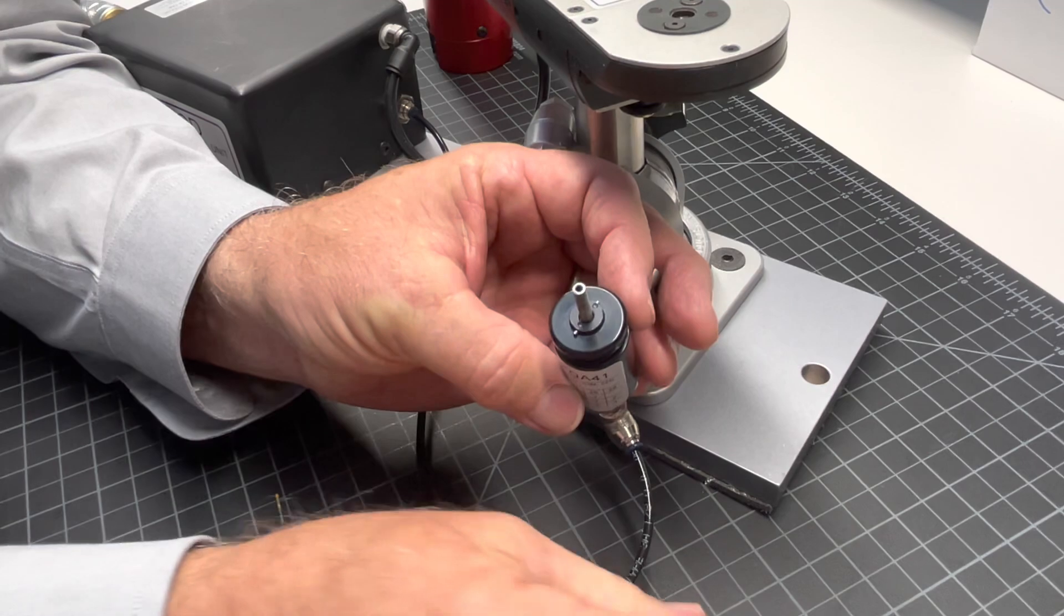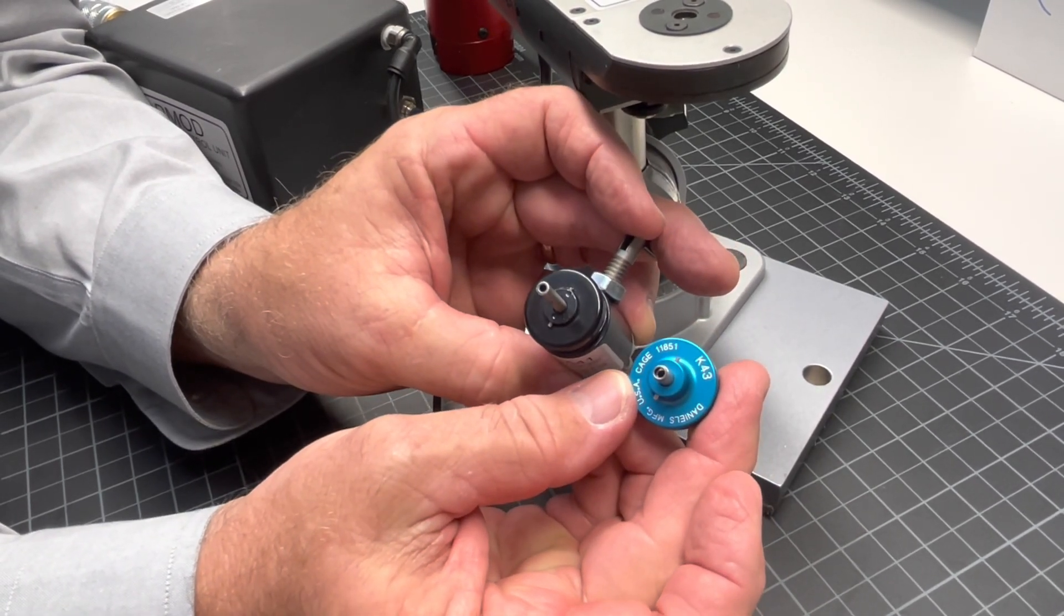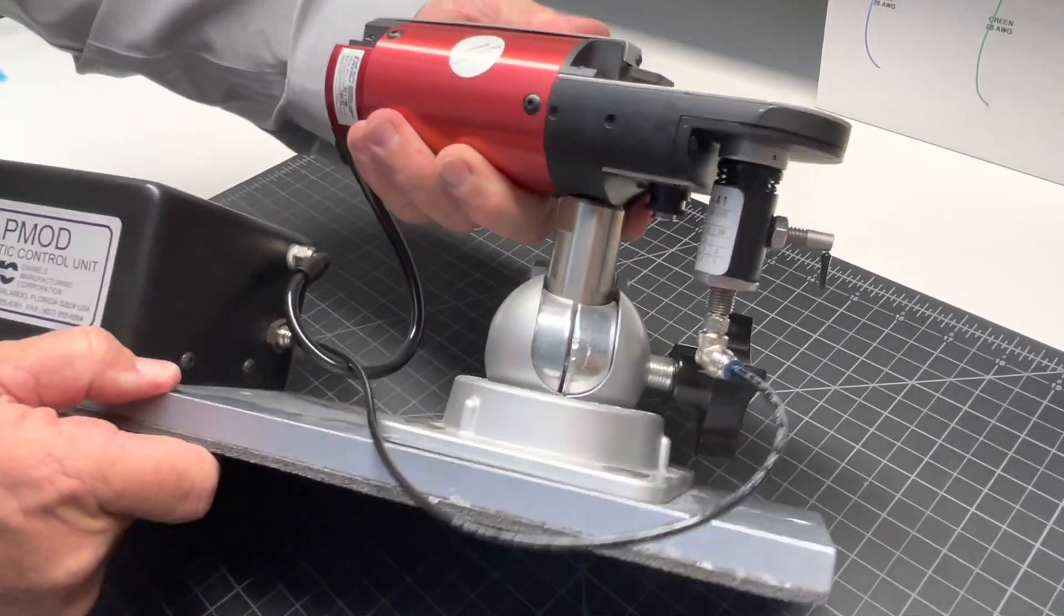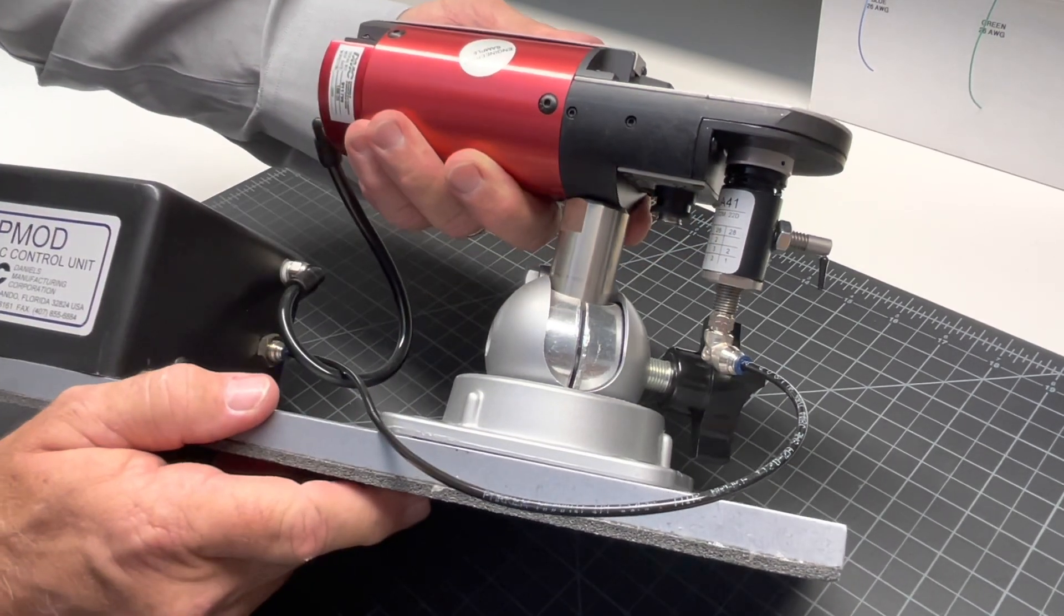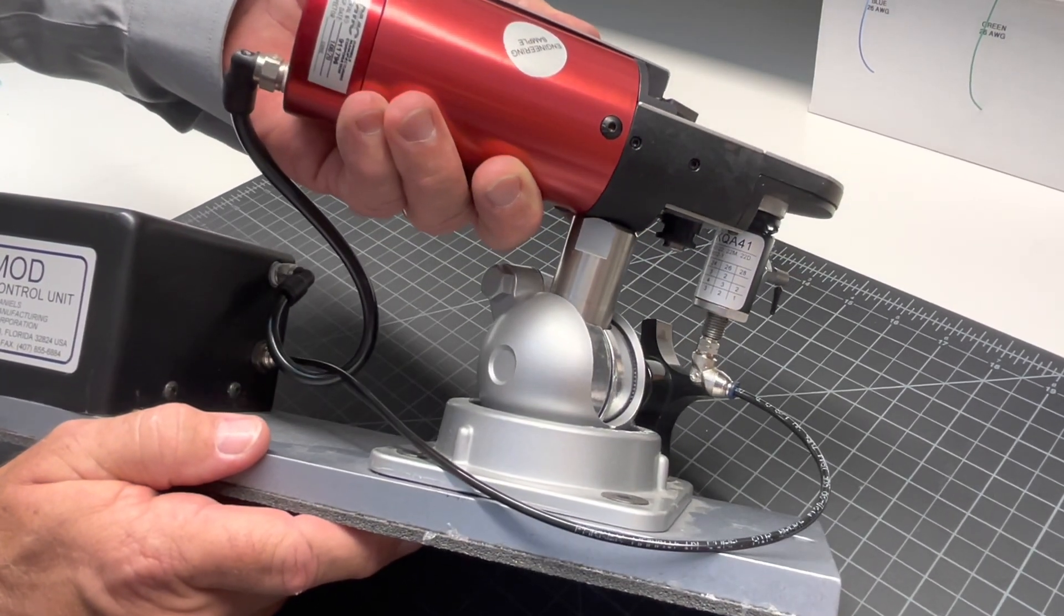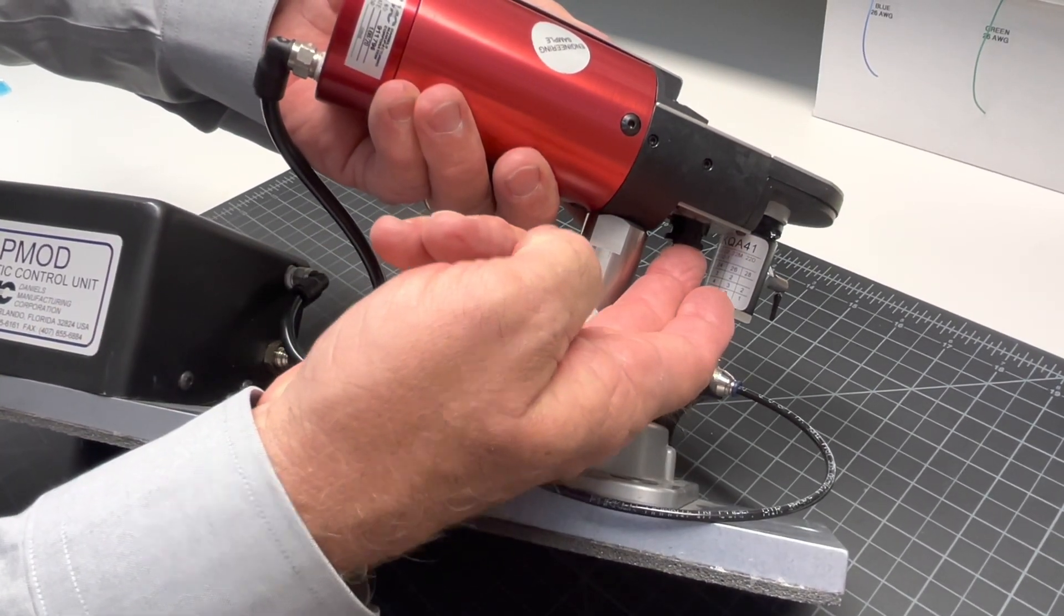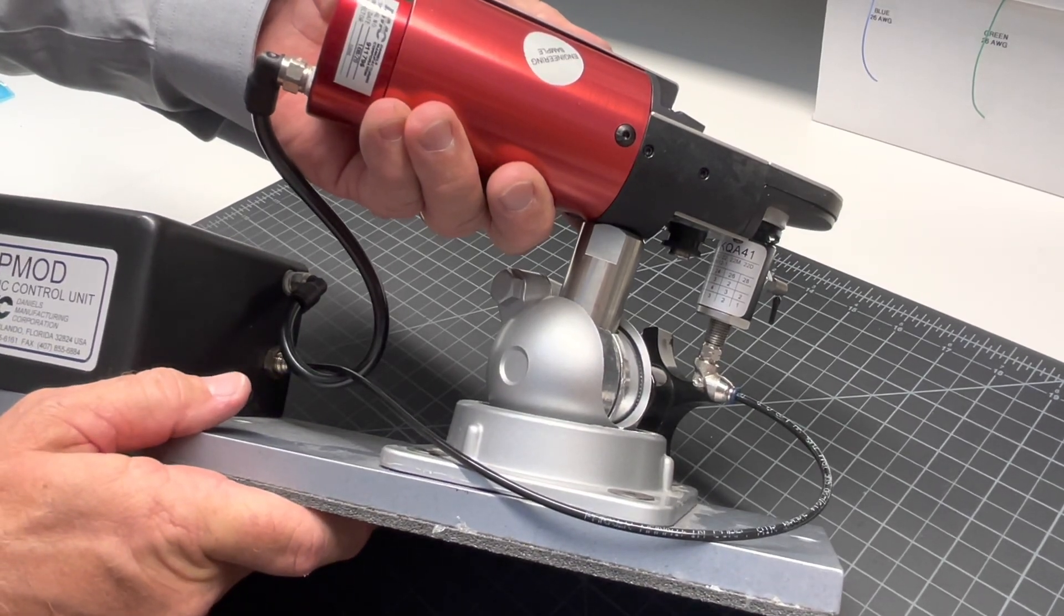They both have bayonet pins and so therefore they install onto the tool the same way. When using the APMOD system, the selector setting will remain the same and the settings will be identical to what you have on your crimp tool and your hand positioner. Make sure you set the selector knob to the proper setting, matching your contact and wire size.